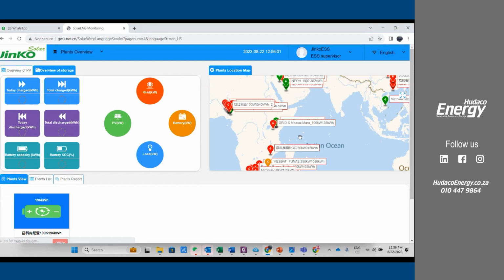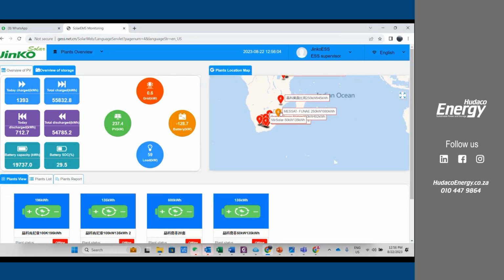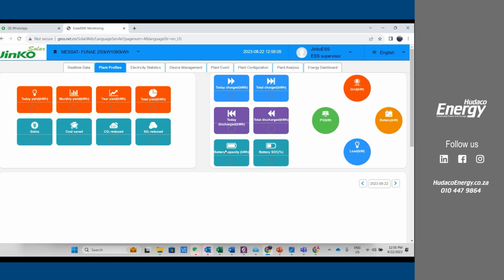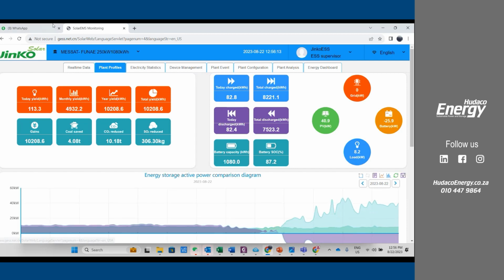Maybe you can open the mic so you can explain adding battery packs, because our string is actually 1.5 kilowatt hours, so we cannot add more than that, since we need to pay attention to the voltage ranges as well. I'm not sure about adding within a rack, because our design is basically to expand from one rack to the next rack, not expanding at the rack level. We need to parallel the racks.